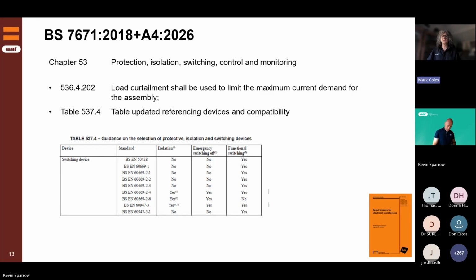Load curtailment means, for example, let's say you've got a heat pump running and EV charging. It might be the EV charger, with the CTs, the current transformers that monitor what's going on, says, hang on a minute, we're getting up towards 100 amps or whatever, I'll ramp it down or I'll switch off completely. That's load curtailment. So what's gone in here is that using that form of technology allows you to dynamically control maximum demand, so you're not going over the top. So that can form part of your designs. That's a really interesting one.